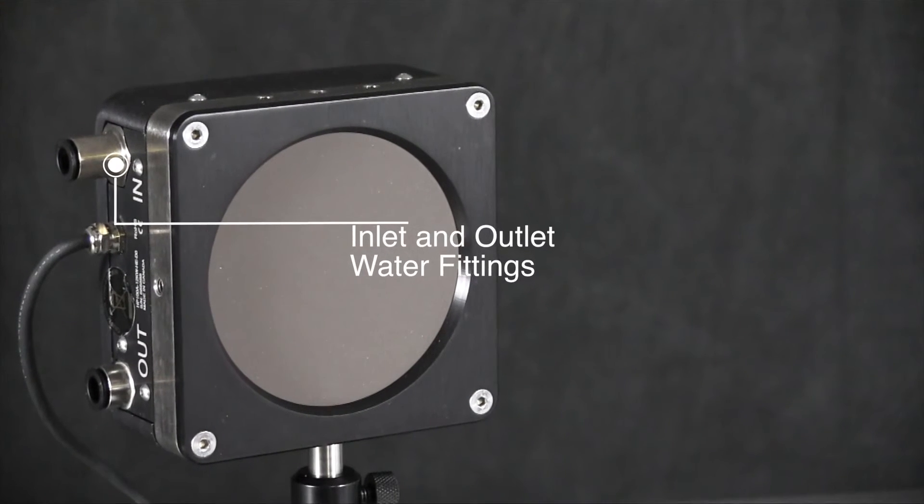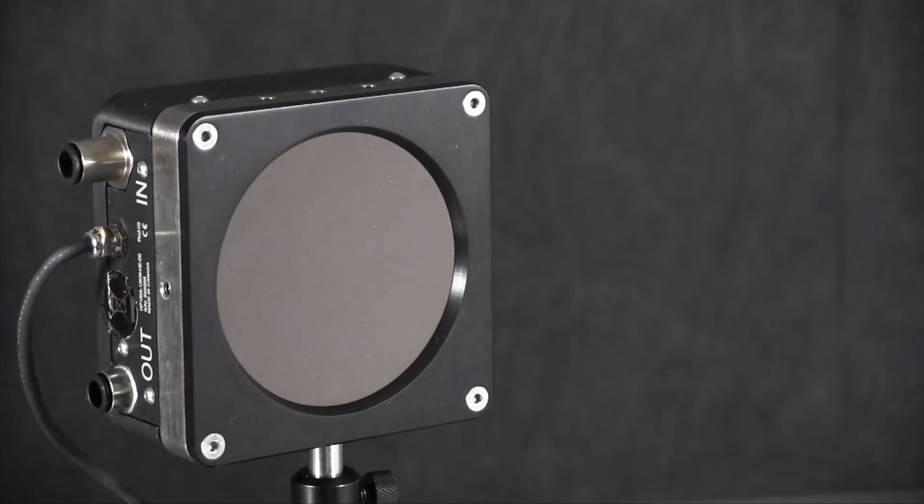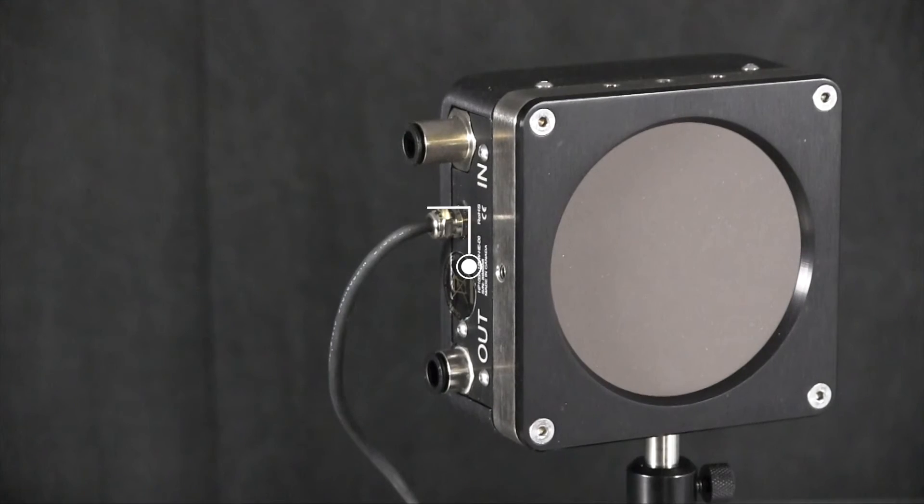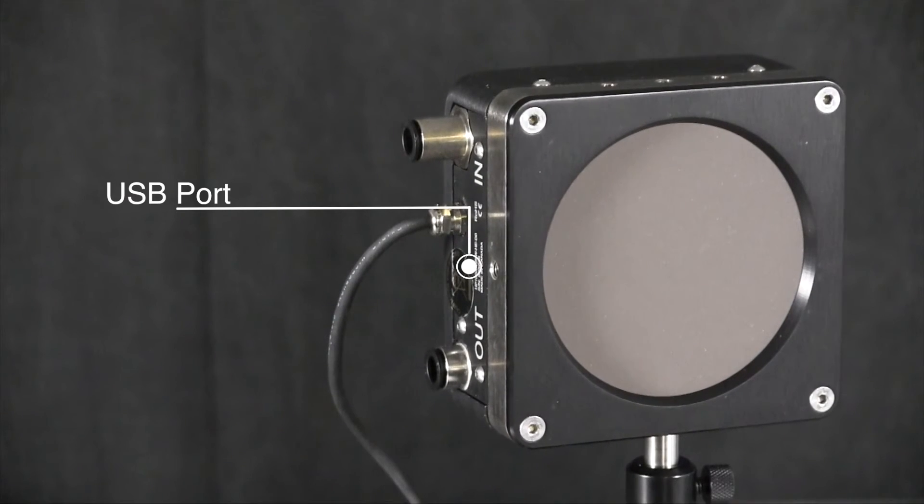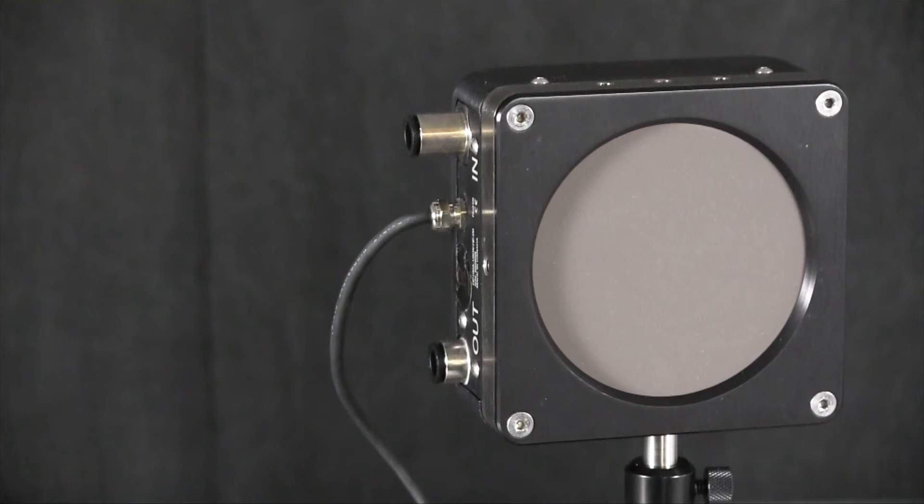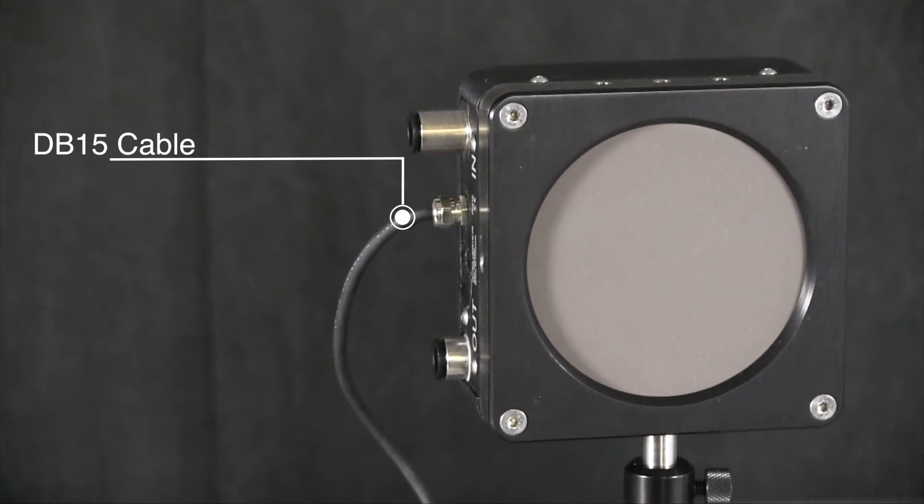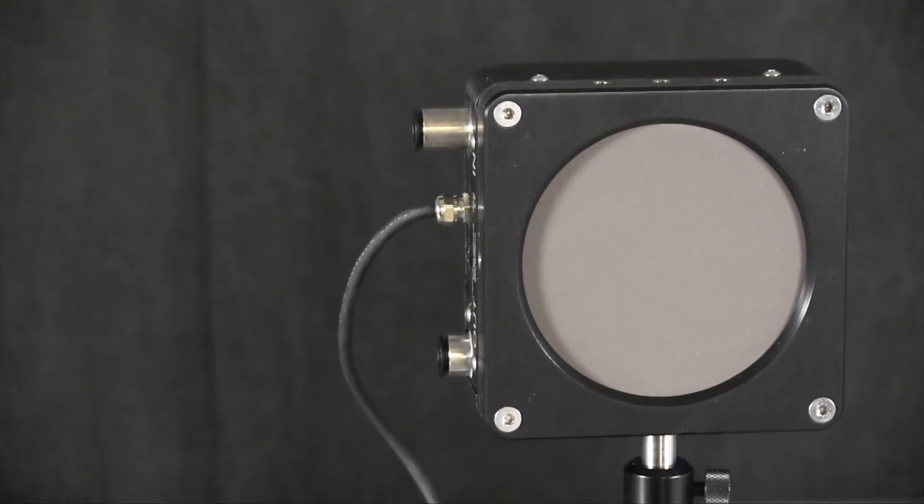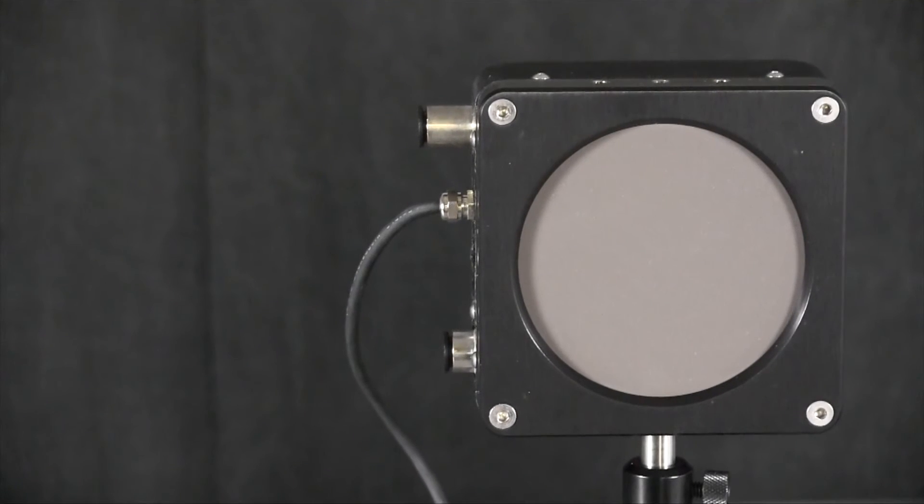On the left side of the probe, you'll find the inlet and outlet water fittings. There is also a USB port should you want to connect the probe directly to your PC. And a DB15 cable so that you can plug the HP into one of our many digital power meters like Maestro.